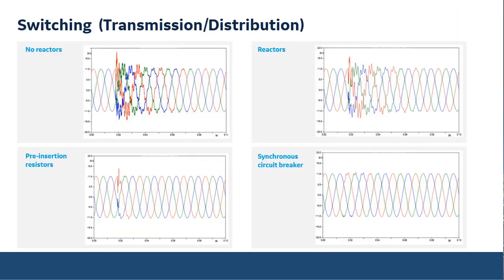Now, talking a little bit about capacitor banks. We do have reactors that are installed with capacitor banks, and the reason for that is to limit the inrush, outrush, or back-to-back current of it. This slide is a more practical slide, comparing a cap bank being switched with reactors, not having reactors, being switched with a type of switcher with resistors, or with a synchronous breaker.